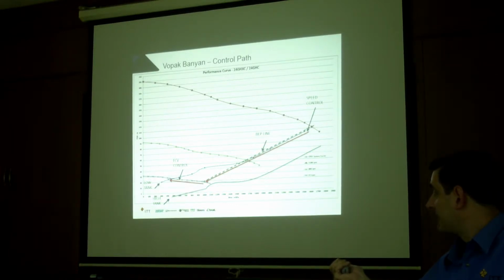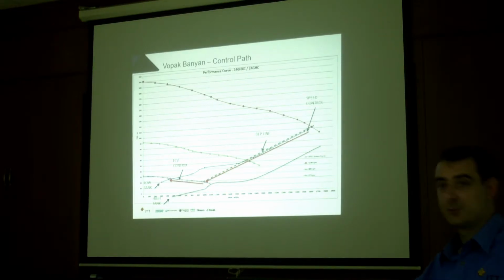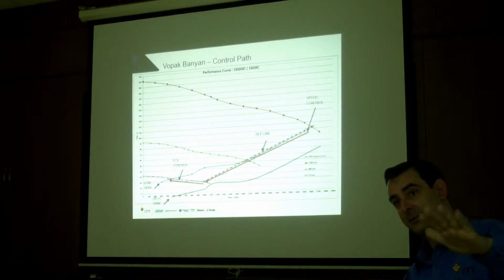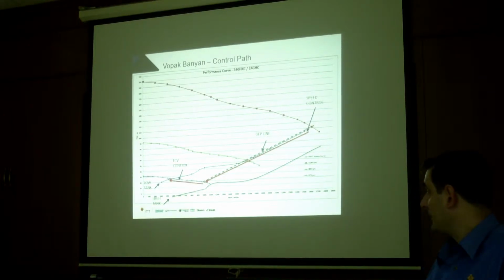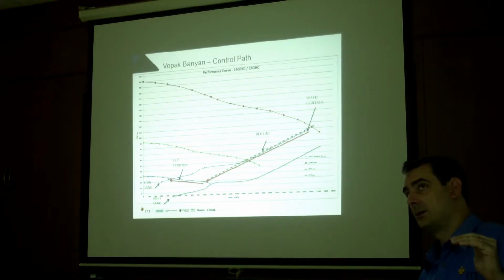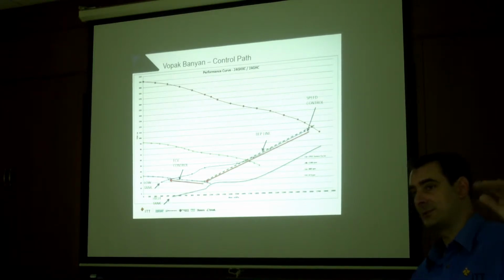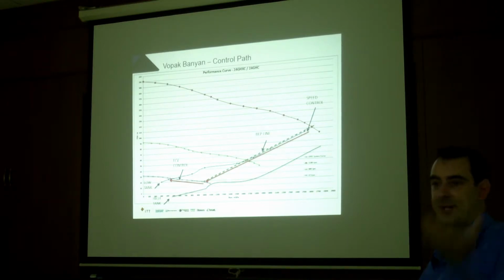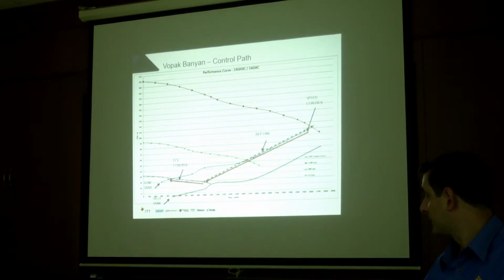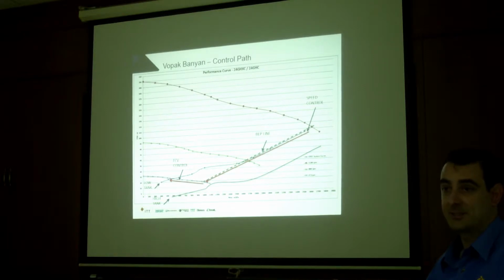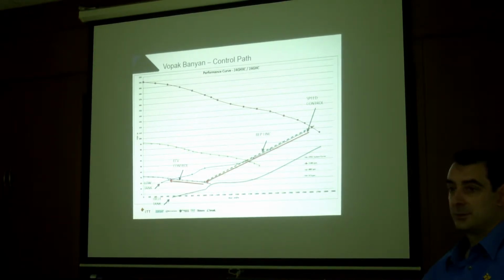And here, this happened during commissioning. They wanted to lower the roof. That's when the roof is going to hit the floor, so they need to make sure it's going slow. We were at 1,000 meters cubed per hour because the intersection from a high tank, which was on, we were pumping from the one high tank to the low tank or something like that. Actually, even when they raise the roof, they need to do it slow. So we were doing 1,000 meters cubed per hour because the system curve intersection with the pump curve was down here. So the only way to do it was to use the flow control valve to bring the flow back.